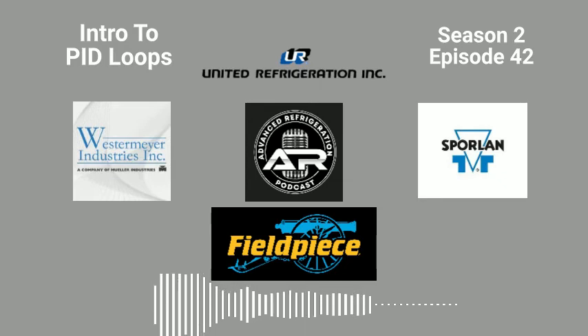I've yet to see a flash tank come out from a factory tuned even remotely. I've yet to see a CO2 flash tank come out even close to what it needs to be. So like we were saying, guys, you need to make sure everything is 100% right before you start trimming back PIDs. Make sure everything is functional, your input is proper, your update rates are good, and everything is set up properly before you start introducing all these PID loops.